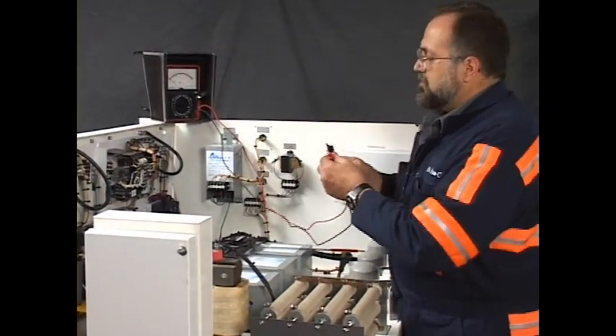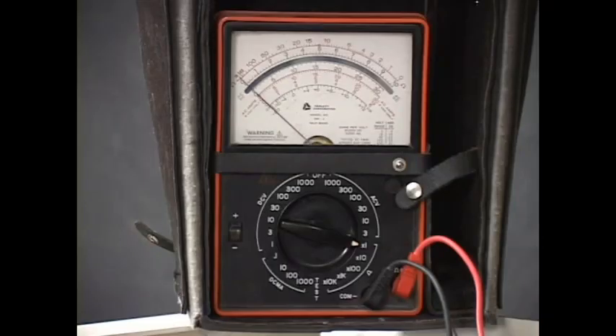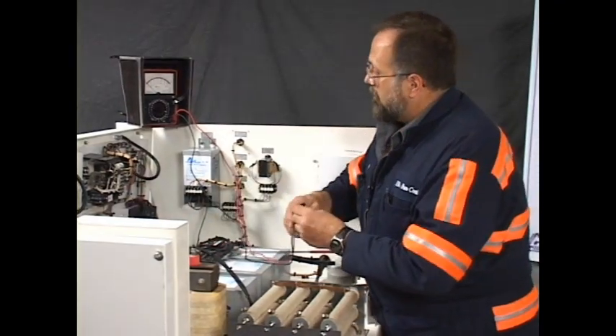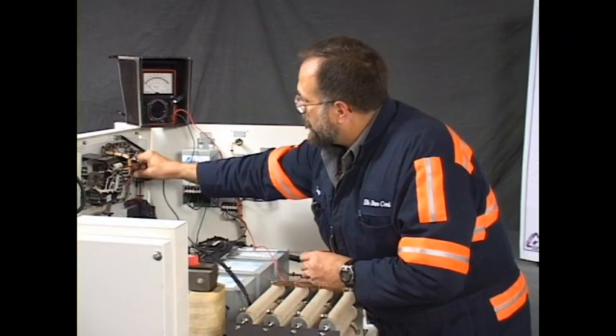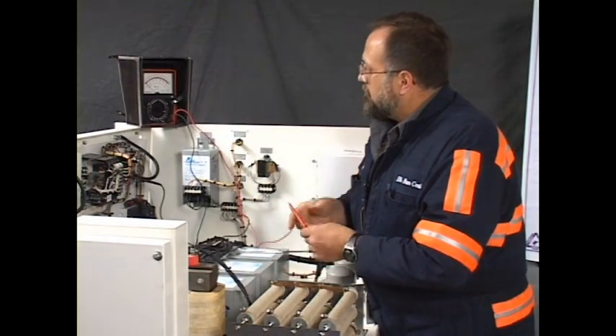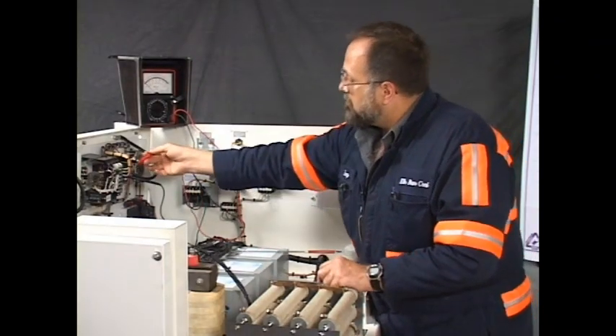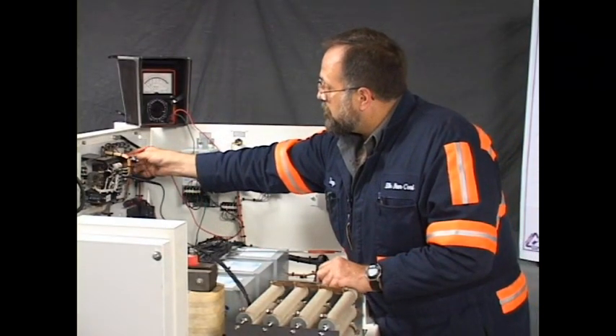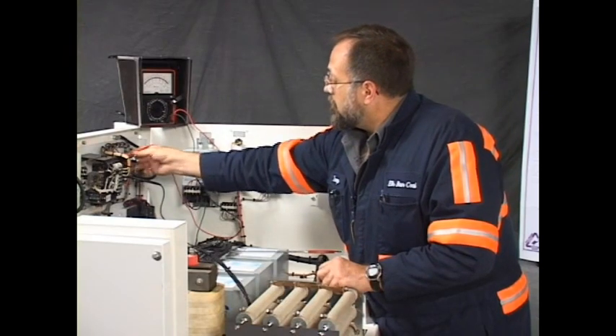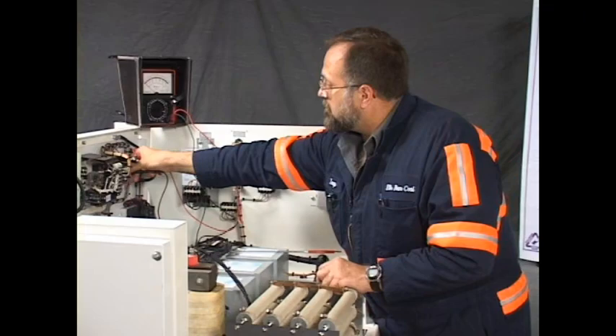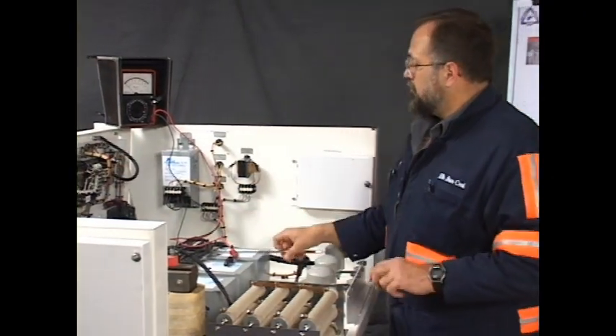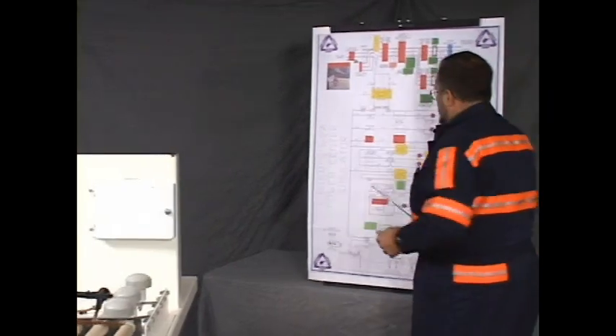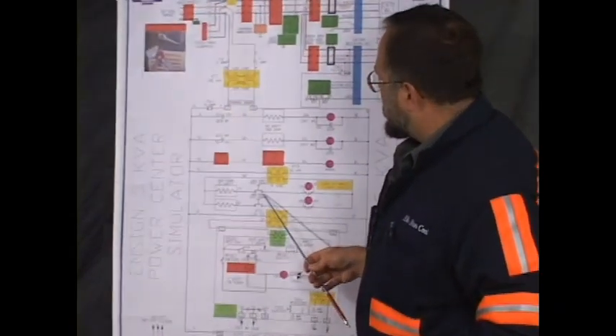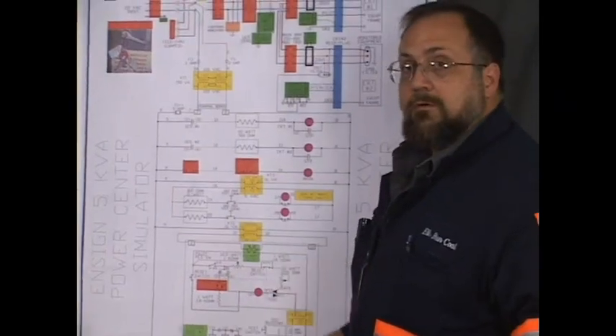The only components that could make these symptoms that we just saw are the ground trip relay contacts. Their reading's unchanged, they still read open. And this GTT. Now you recall, when the switch was depressed, it read 0 ohms resistance. In its normal status, it read 9 ohms. And there you have it. It reads a dead short, 0 ohms resistance. So our problem: the normally open ground trip test switch for circuit number 1 is shorted.